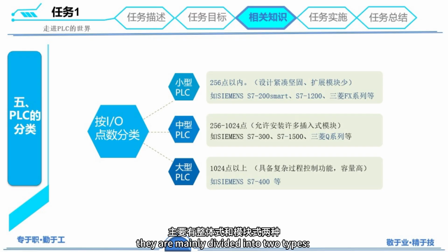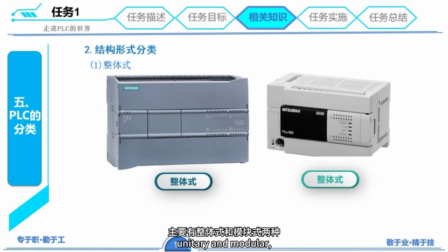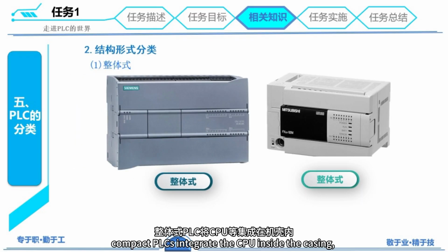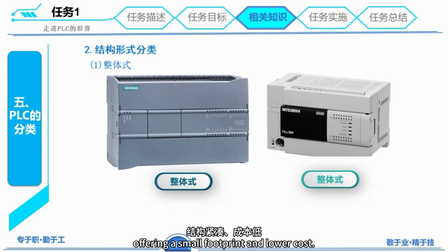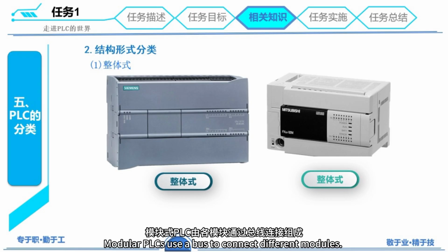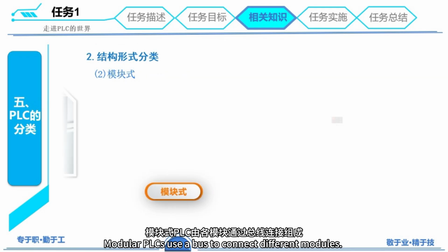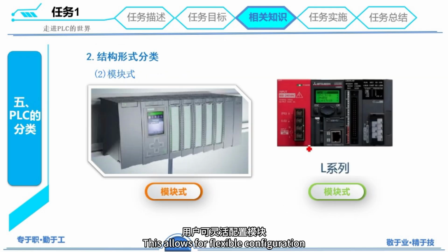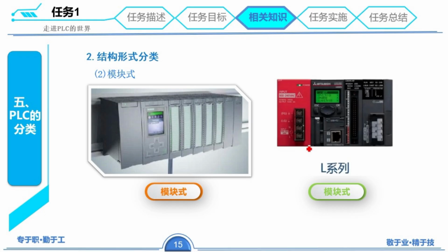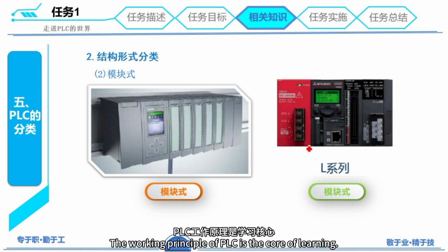Based on their structure, they are mainly divided into two types, unitary and modular. Compact PLCs integrate the CPU inside the casing, offering a small footprint and lower cost, such as the Siemens S7-1200, ideal for small applications. Modular PLCs use a bus to connect different modules. This allows for flexible configuration and easy expansion, like the Siemens S7-300, perfect for medium and large systems, with flexible maintenance and easy upgrades. The working principle of PLC is the core of learning.